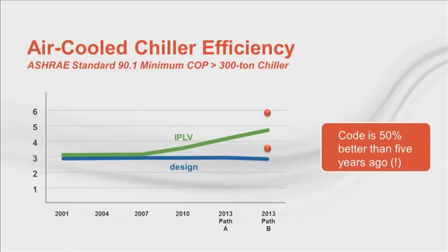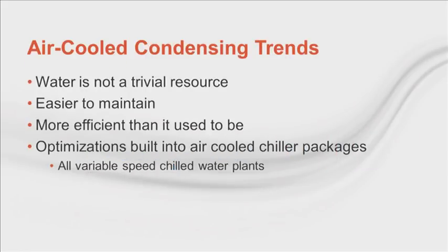The dots represent data from premium efficiency chillers, one selected for very high full load and part load performance. What does this tell us? There remains additional chiller efficiency levels to design into chiller plants. In fact, over 25% higher full load and 45% higher part load efficiency. And this is even more significant because the performance levels don't rely on higher level control optimizations. Most of the optimizations for the all variable speed air-cooled chiller system are inside the chiller controller itself, as standard from the factory.